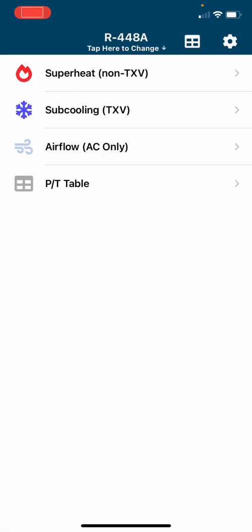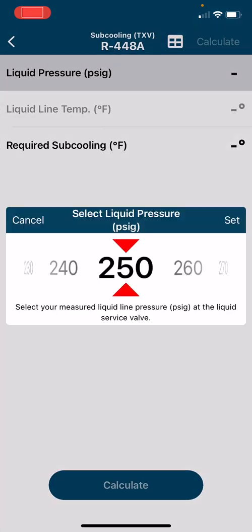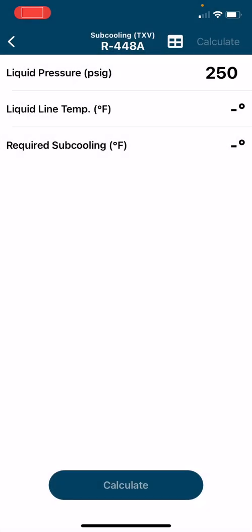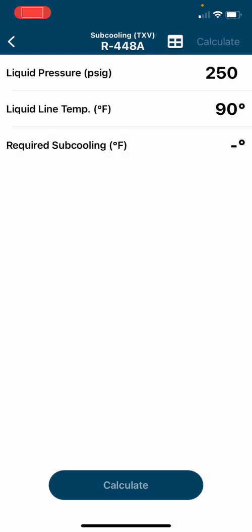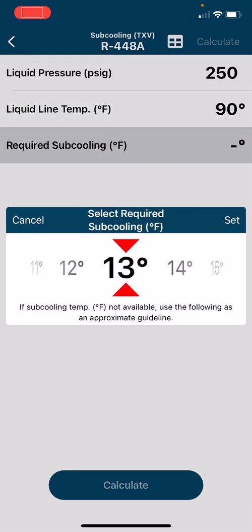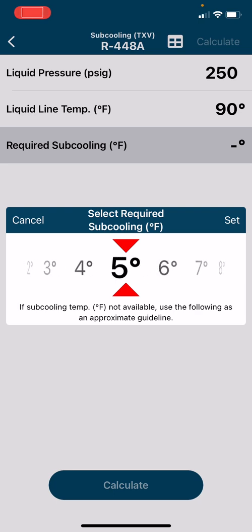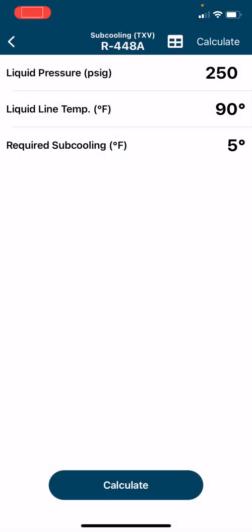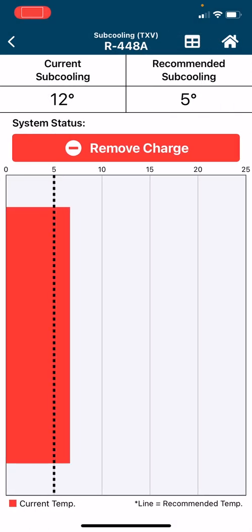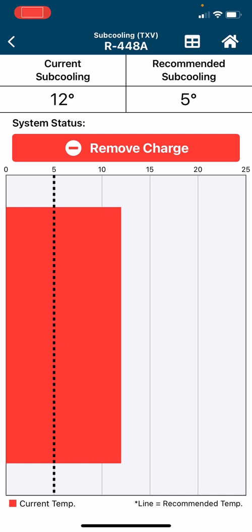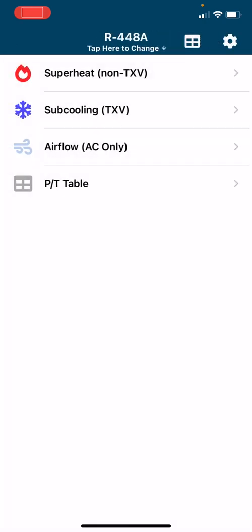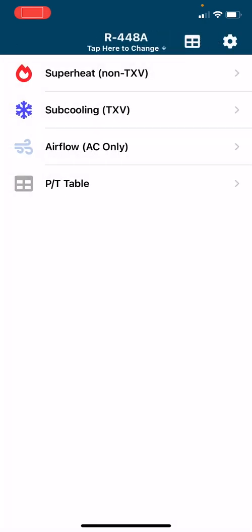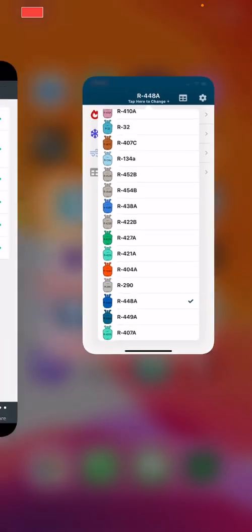We will do a quick example here. TXV, say it is a TXV. We will do the liquid line pressure, we are just going to say it is 250, liquid line temp 90. We will say required subcooling, we will say we are looking for 5 degrees, that is what we want, set. We go calculate. We have too much charge in there, we should remove some of the charge. So this is just a quick app to do that with many, many different refrigerants. Many different refrigerants as you can see.